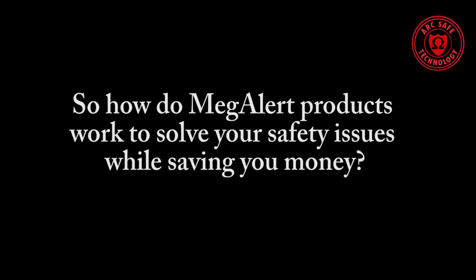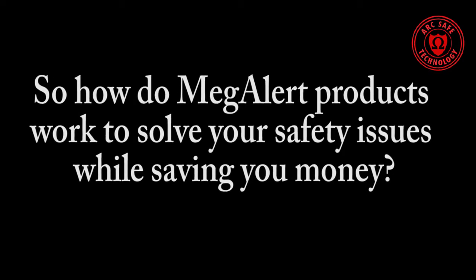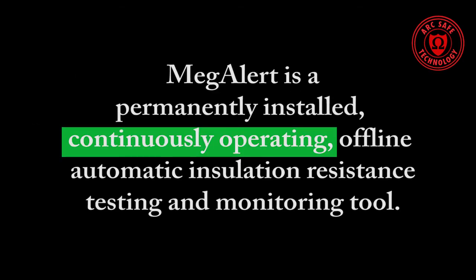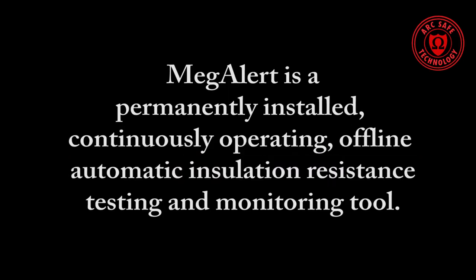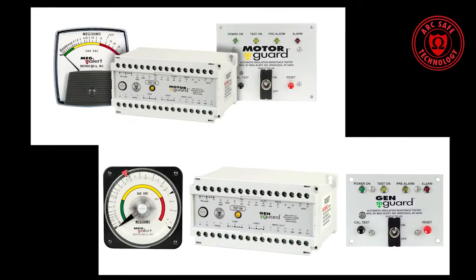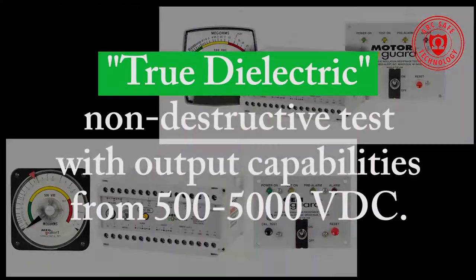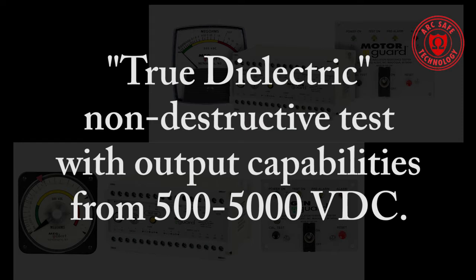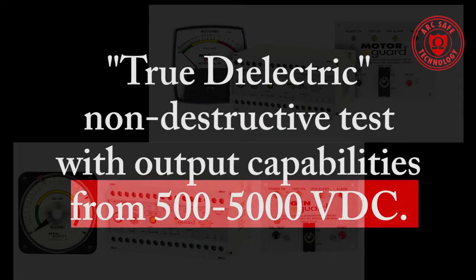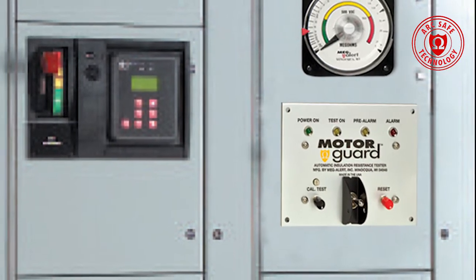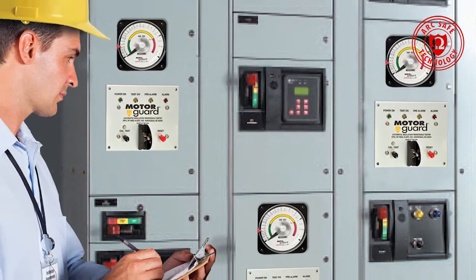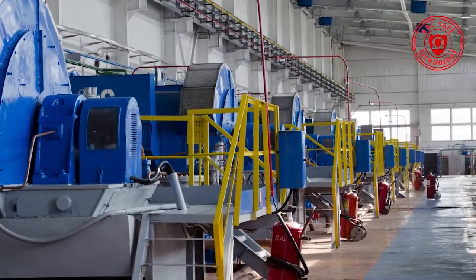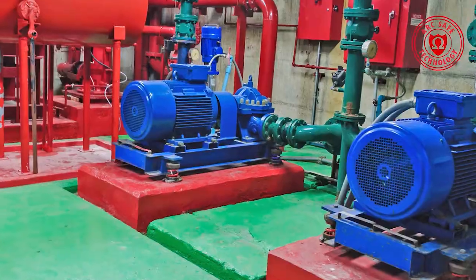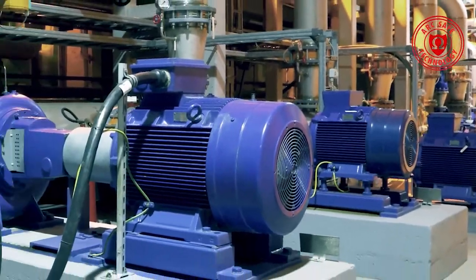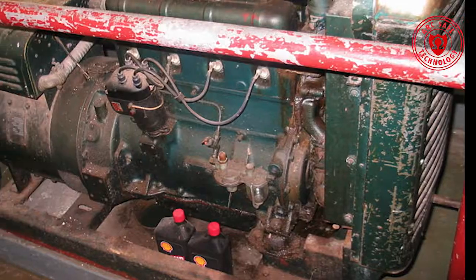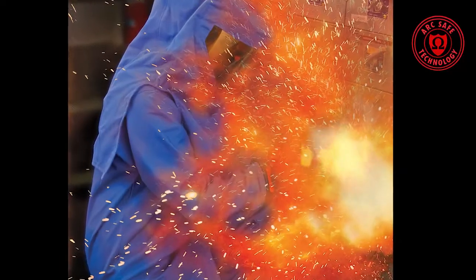So how do MegAlert products work to solve your safety issues while saving you money? MegAlert is a permanently installed, continuously operating, offline automatic insulation resistance testing and monitoring tool. Our MotorGuard and GenGuard systems provide a true dielectric non-destructive test with output capabilities from 500 to 5,000 VDC. MegAlert's patented continuous, offline, hands-off testing will protect all types of critical equipment operating from 120 volts to 15 kV, while significantly reducing catastrophic repair costs, unscheduled downtime, and providing arc flash mitigation.